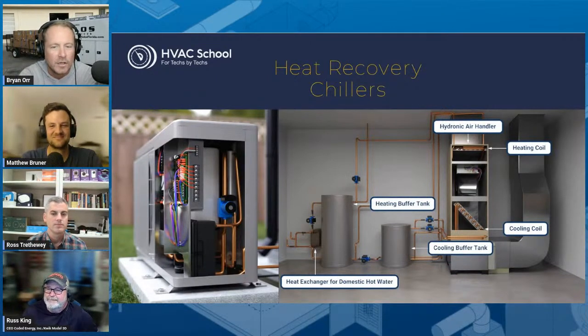But I think if we wanted to have the world's perfect setup, we wouldn't even have this outdoor air source unit. We would have a combination of ground loop and this indoor hot, cold buffer tank, domestic hot water, sort of the magic box design. One of the big things it solves for, because when people see this, they're like, I don't get it, is that you can do simultaneous cooling and heating. So now this system becomes a dehumidifier as well.